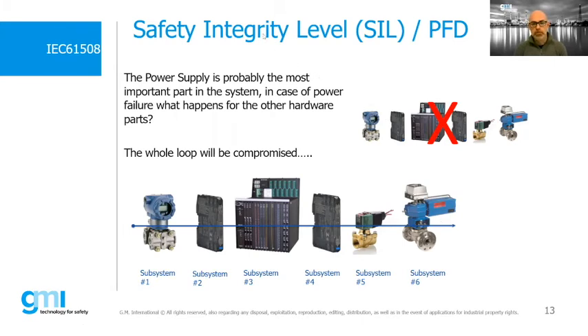Within this safety loop, we have field devices such as transmitters or sensors, which allow us to control, detect, and measure variables in the field, such as temperature, pressure, or others. They are driven by barriers or isolators that limit the current towards the hazardous area or isolate field instruments. In turn, the signals sent by the field loop are acquired, managed, and interpreted by the brain of the SIS, the PLC-DCS system, which decides on any action to be taken to make the plant safe. And again, power interfaces such as a safety relay connect to a valve and an actuator, which allow us to bring the system to a safe state in case of need.